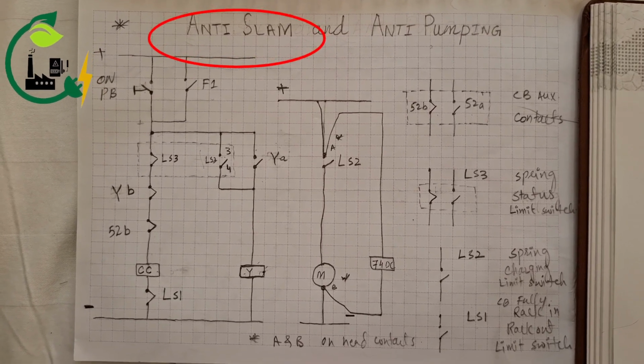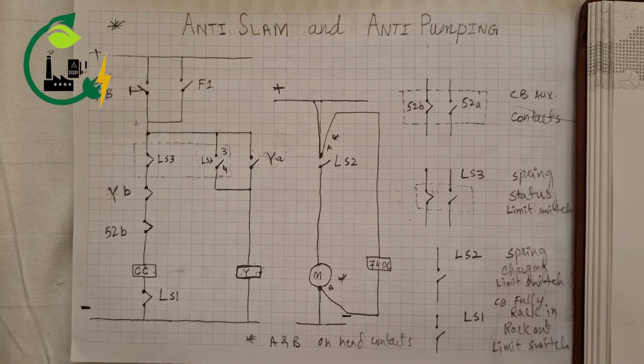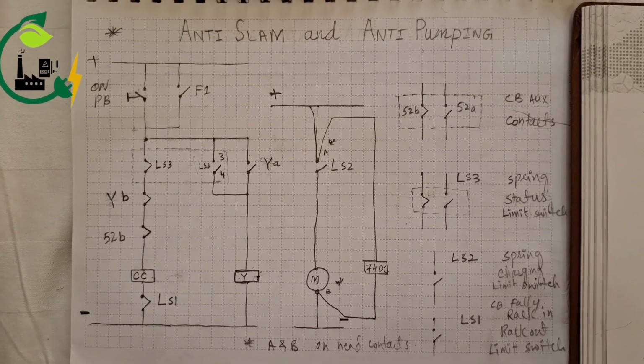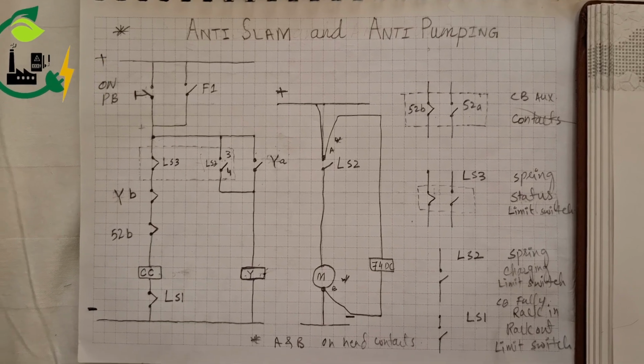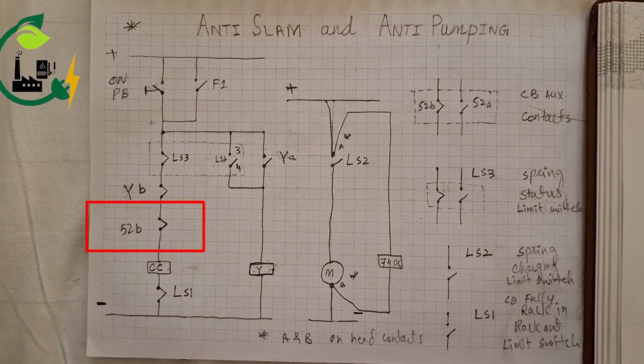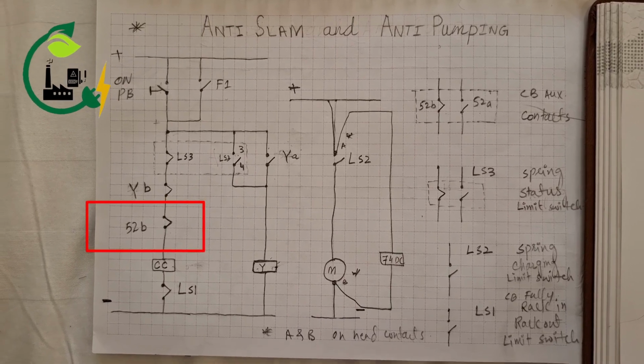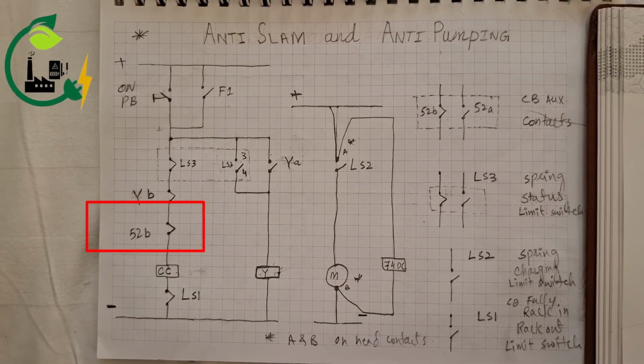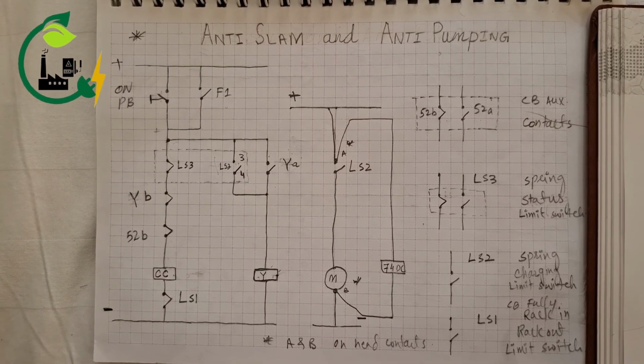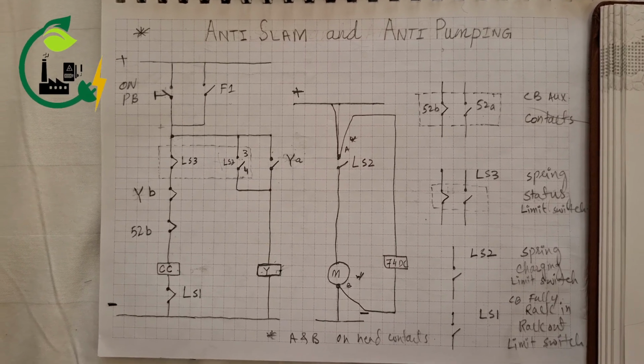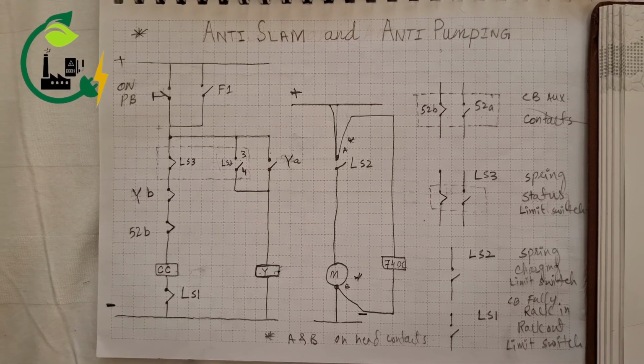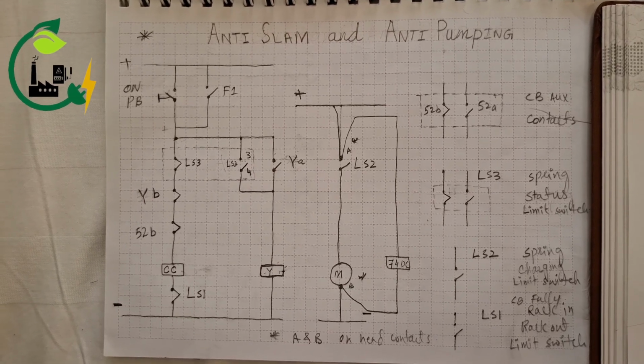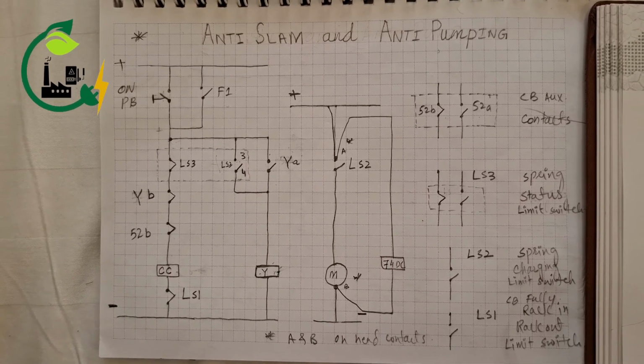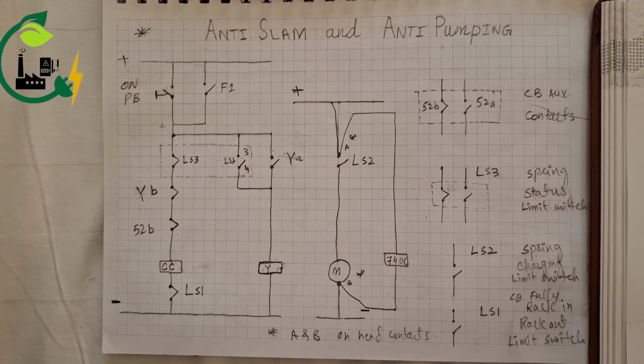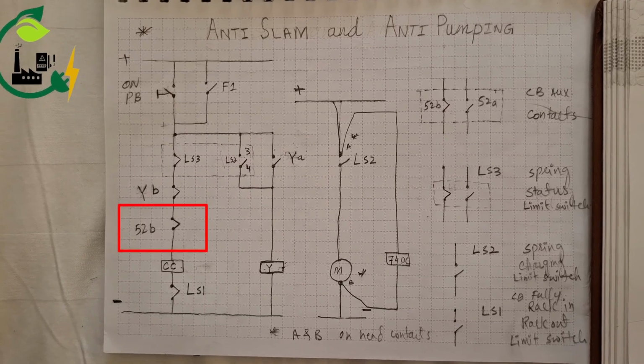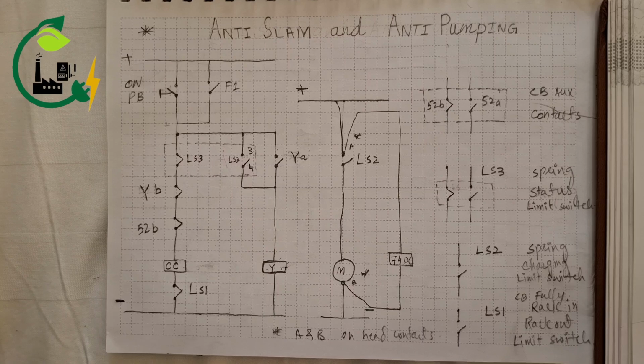Anti-slam contact is nothing but a simple normally closed auxiliary contact of the circuit breaker whose coil we want to protect. So we put a normally closed contact. Here you can see the 52B contact in series with the closing coil. If the circuit breaker is open, it will pass the supply, because it is a normally closed contact while the circuit breaker is open. So once the circuit breaker is open, we can give the supply to the closing command. Once we give supply to the closing command, the circuit breaker will close and this 52B will open and prevent our coil from being damaged.